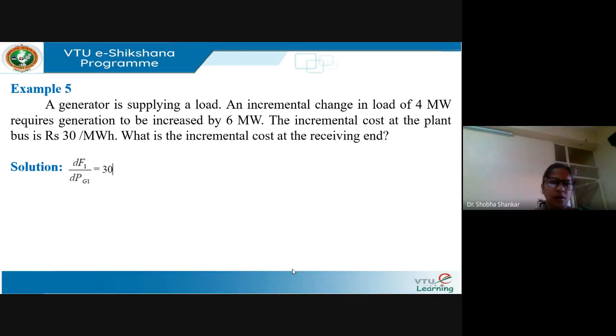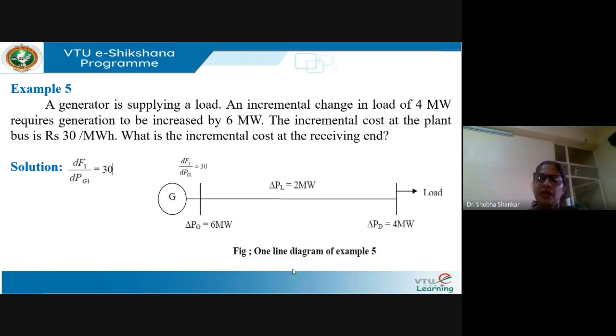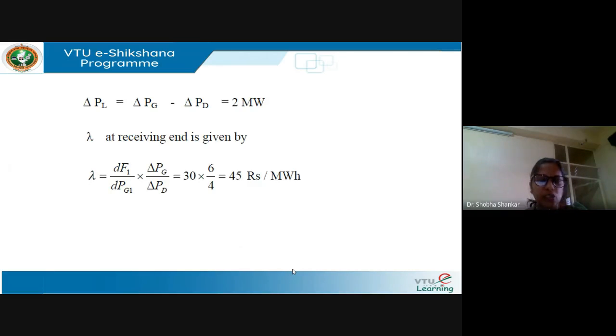Given: at the plant bus, since there is only one generator at bus 1 and the load is at bus 2, dF1/dPG1 equals 30. From the one-line diagram, if there is an incremental change in load of 4 MW, generation must increase by 6 MW, meaning the incremental power loss in the transmission line is 2 MW. So delta PL equals delta PG minus delta PD equals 2 MW. Lambda, the incremental cost at the receiving end, equals dF1/dPG1 times (delta PG / delta PD), giving lambda equals 45 rupees per MWh.